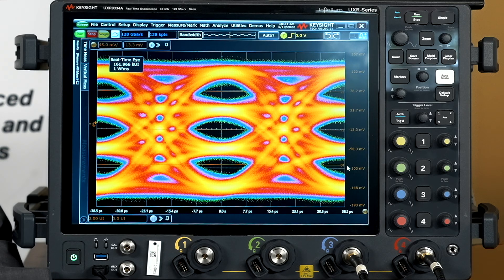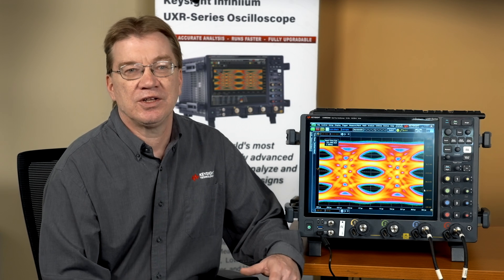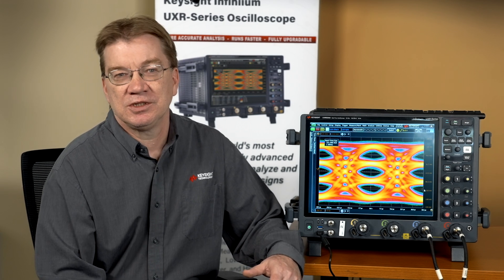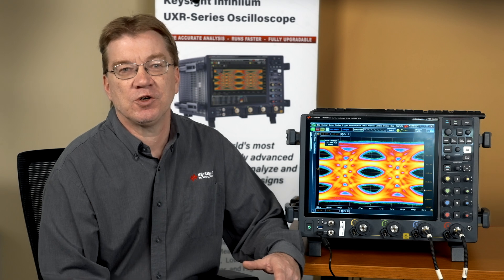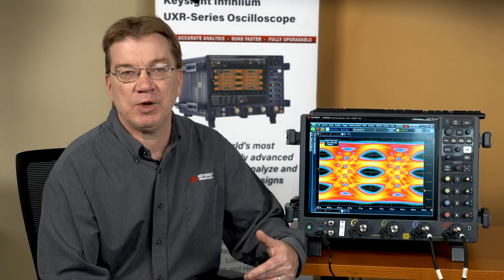The Infinium UXR series, with its industry-leading signal integrity, is the best instrument to perform PAM measurements. The UXR scope owns the best ENOB — effective number of bits — in the current real-time oscilloscope market, with the lowest jitter and the lowest noise. For PAM analysis, oscilloscopes need to determine the PAM levels and the thresholds that separate them, to display a PAM real-time eye, make eye measurements, perform jitter and noise measurements, and recover the clock from the PAM signal.